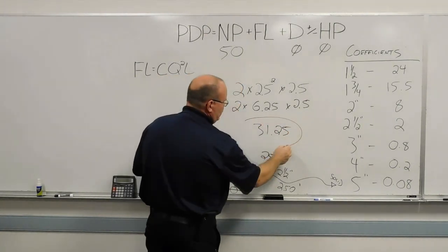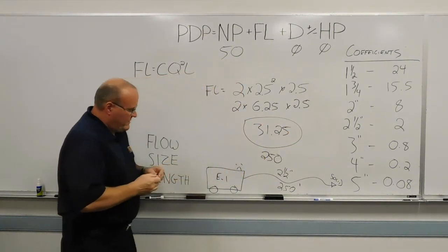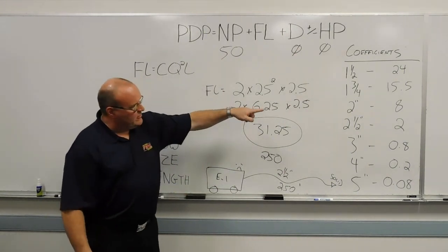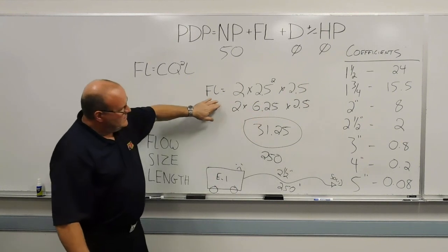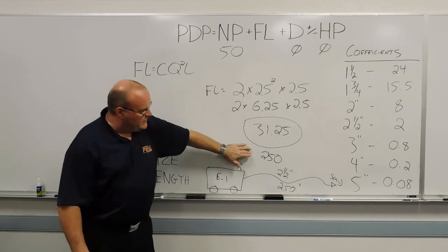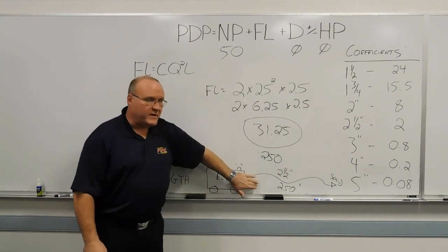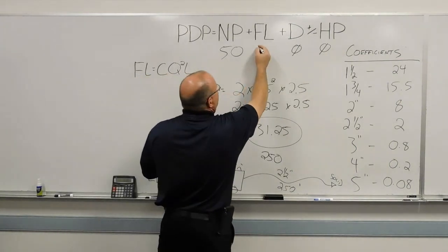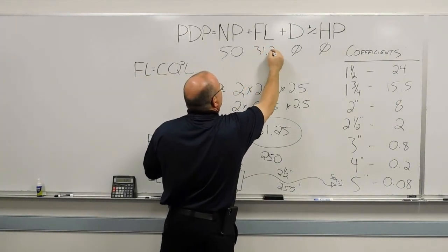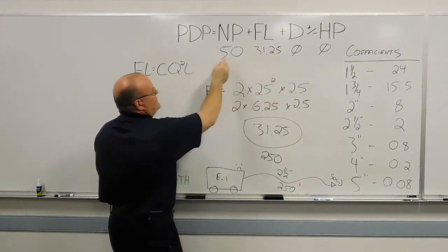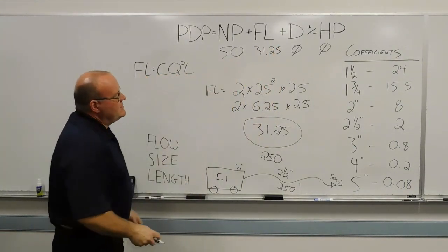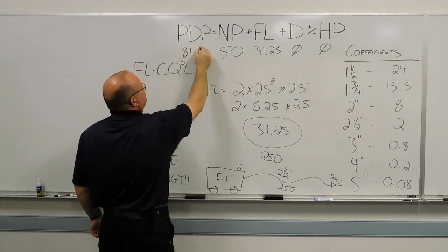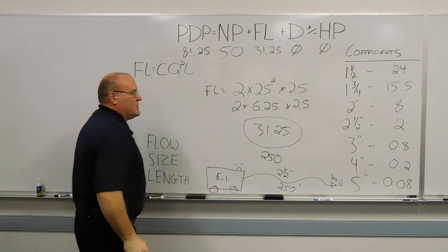So the total friction loss, using the coefficient method, from the discharge to the nozzle, using the coefficient of 2, gallon per minute of 250, length of 250 feet, 31.25. So we'll plug that up here in our friction loss. Add those two together because there's no devices and no head pressure. So we end up with 81.25 pounds pump discharge pressure.